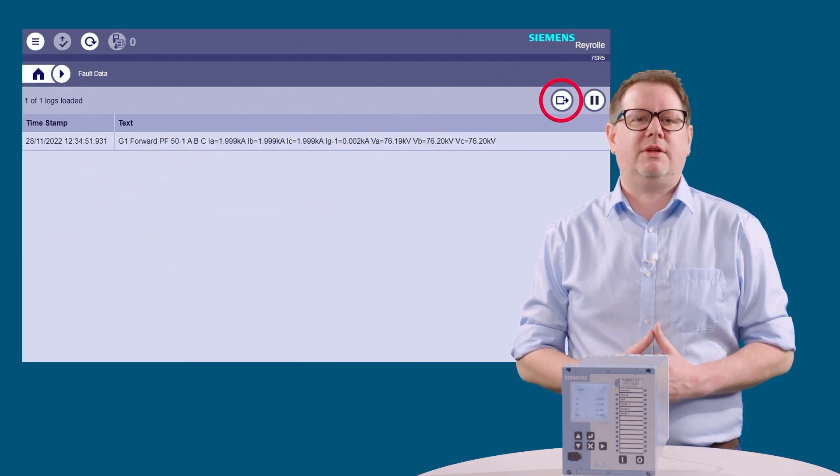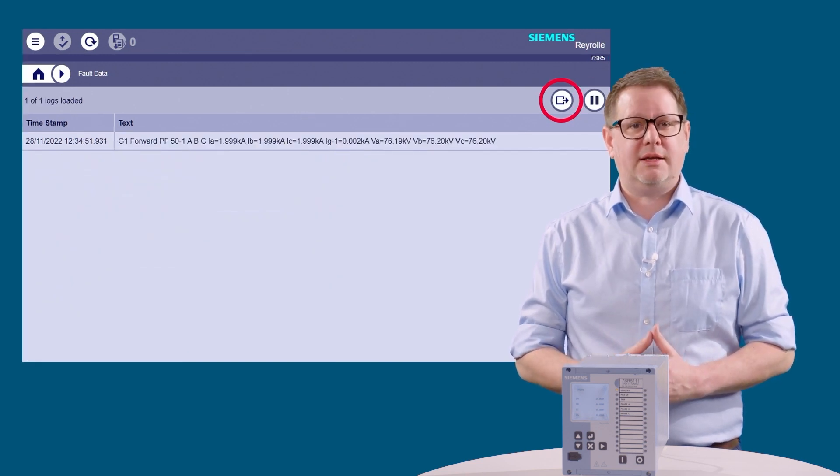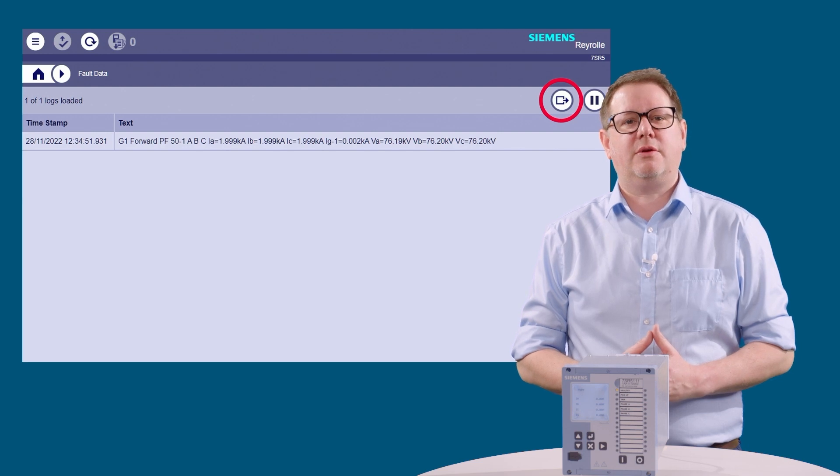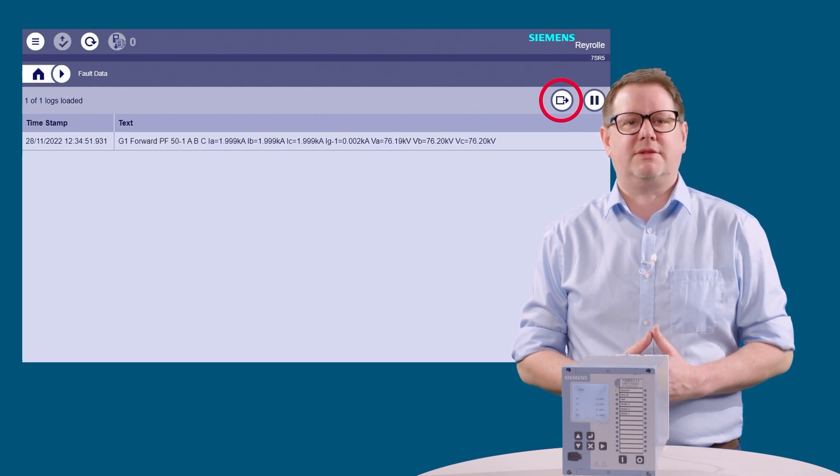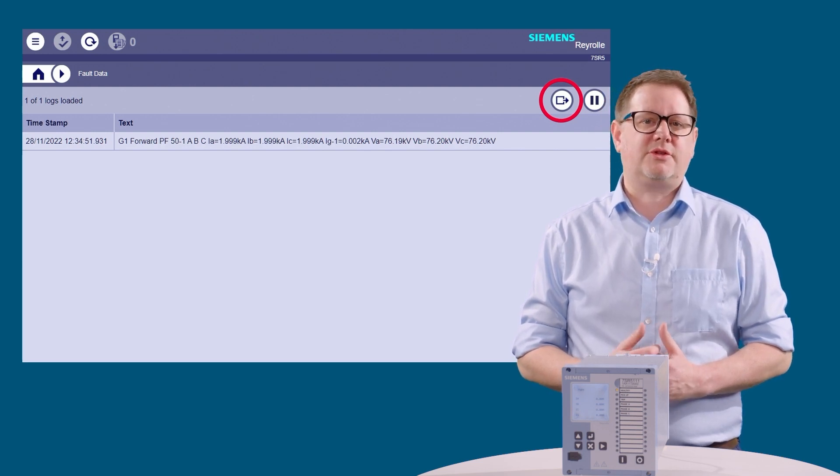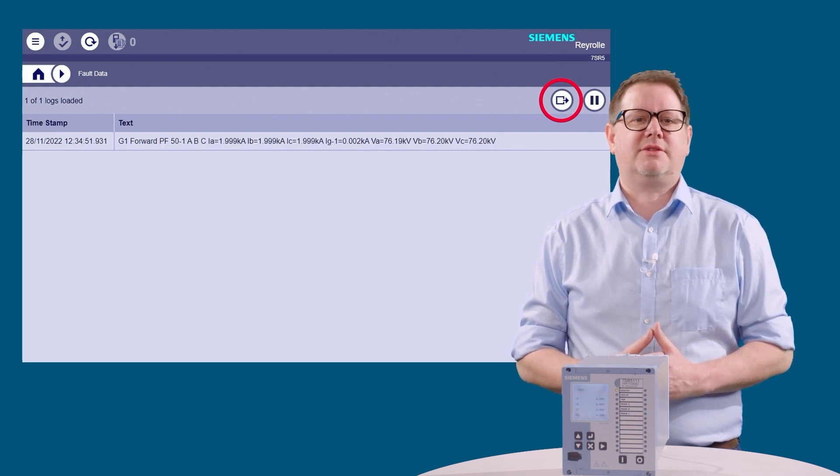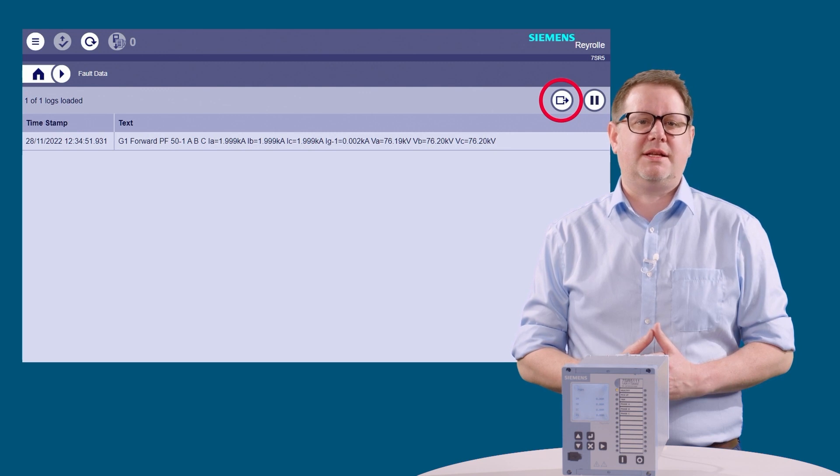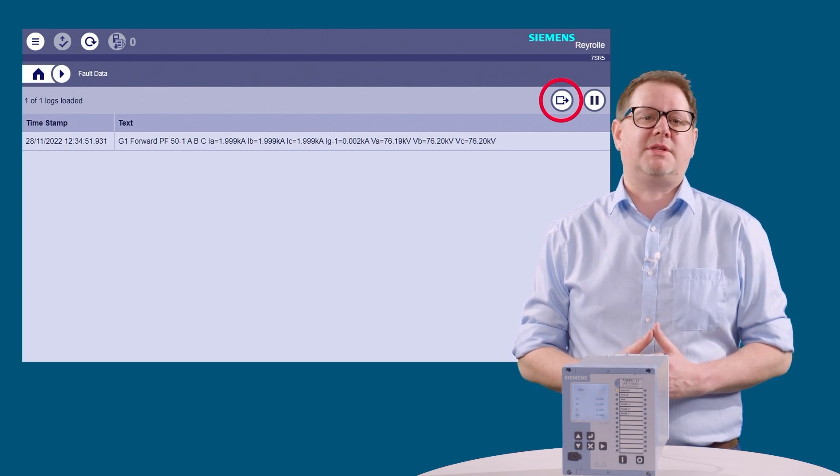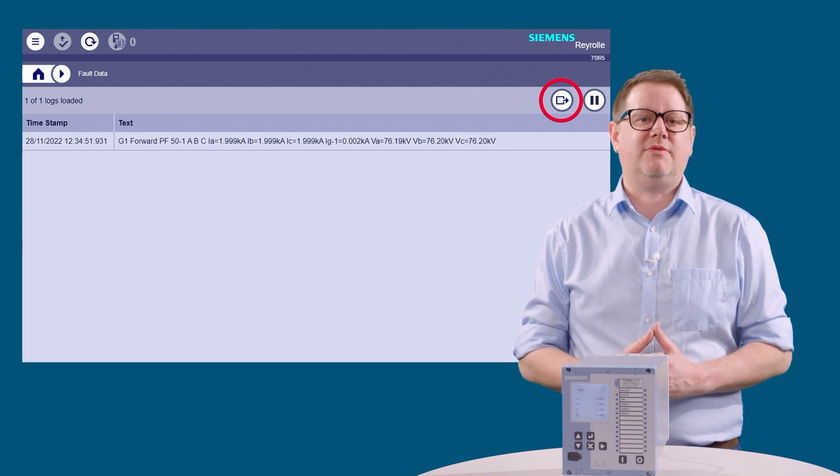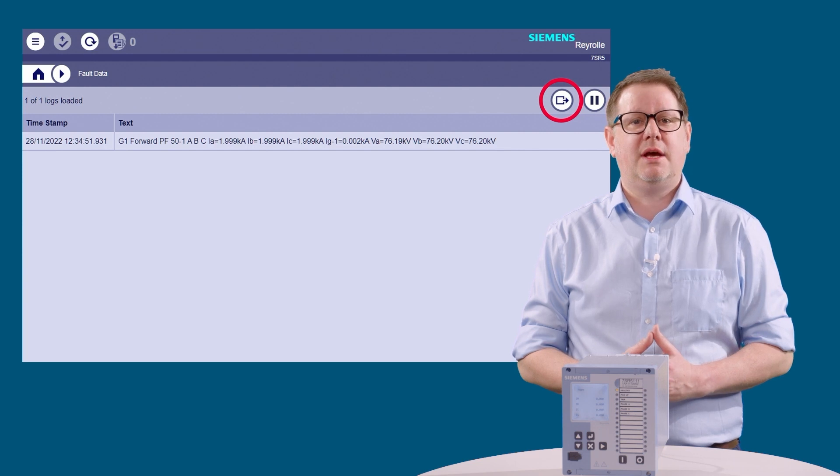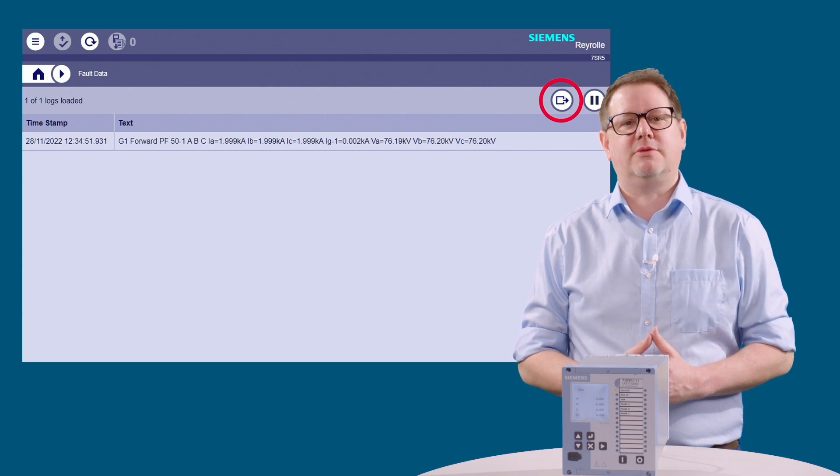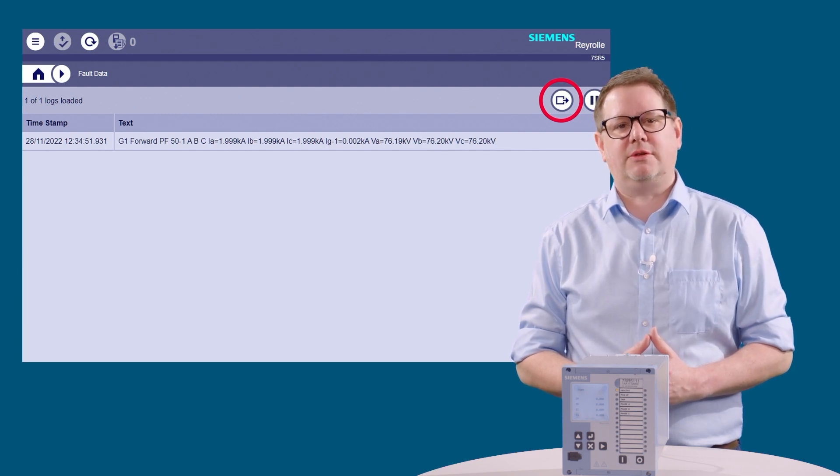Moving on to look at the fault data, clicking the fault data icon will display the data log for the device. Faults stored in the device are displayed in a list here. Each fault is timestamped and contains information on which elements operated and the measured values at the time of fault.